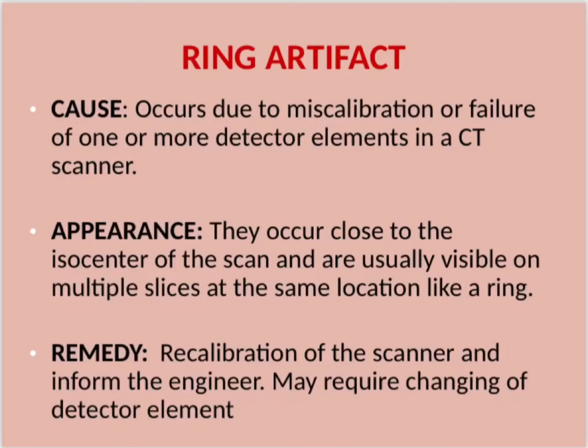Ring artifact occurs due to miscalibration or failure of one or more detector elements in a CT scanner. They appear close to the isocenter of the scan and are usually visible on multiple slices at the same location, like a ring. Remedy: recalibration of the scanner; inform the engineer, as it may require changing of the detector element.